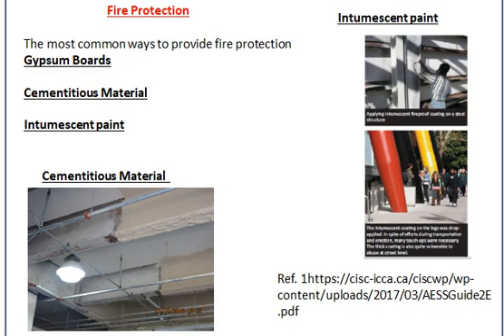If the building is exposed and should look nice from an architectural point of view — such as a library, university, or airport — then we have to use intumescent paint. In this picture you can see the application of intumescent paint on a steel member, and in the other picture the final product after applying it. These pictures are taken from a CISC Canada PDF reference about exposed structural steel, which is a very interesting topic and I recommend everybody download and read it.